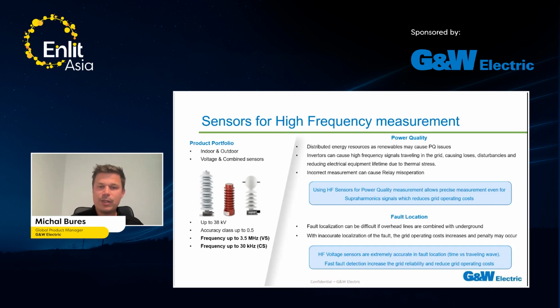Using these high frequency sensors for power quality measurement allows us to precisely measure the supraharmonic signals, and of course, thanks to this, we can reduce the grid operation cost. Additionally, there is one more thing. Thanks to the high frequency measurement, we can do very precise fault location because we have a high sampling frequency. We can compare time versus travelling wave and locate the fault more precisely. So if we have some fault in the grid, we can locate it very fast and repair the line very fast. It's something that utilities definitely need.